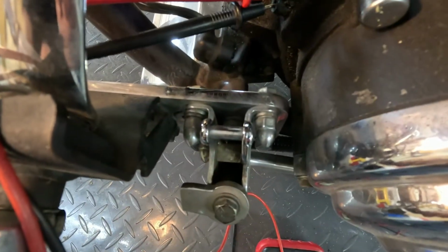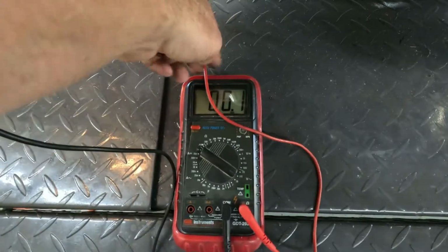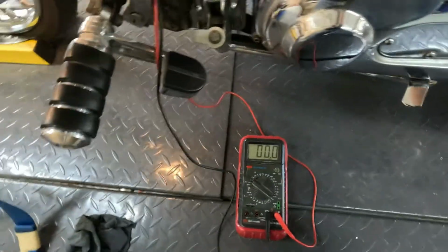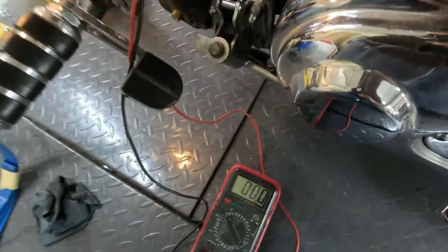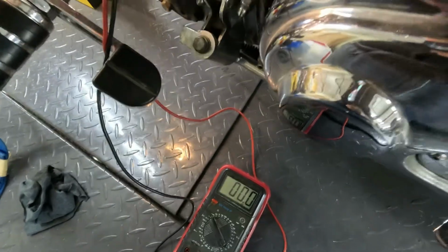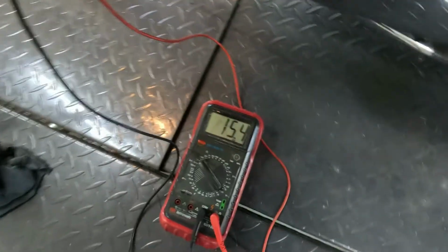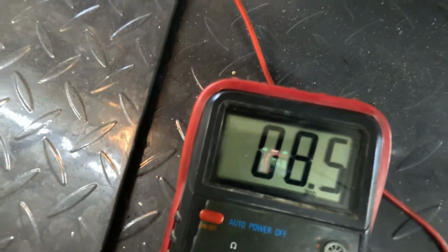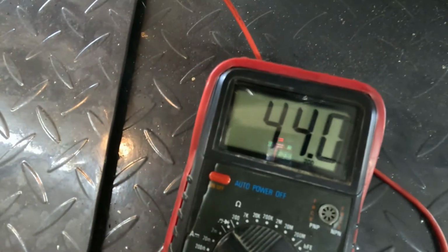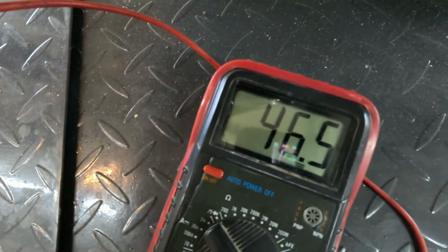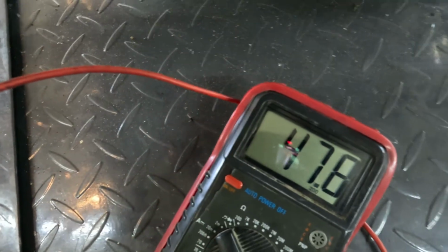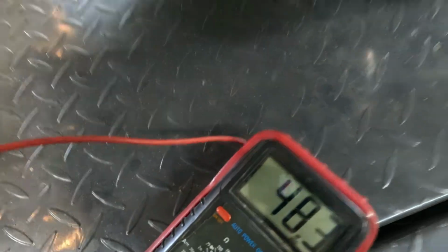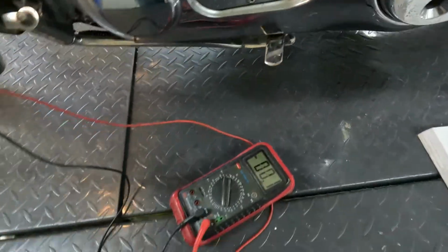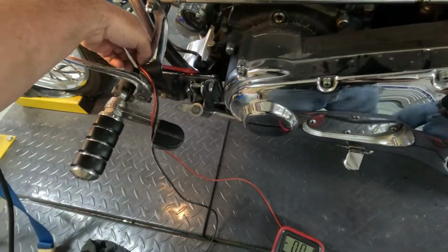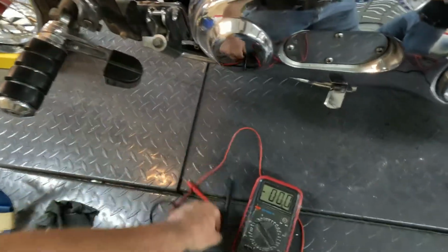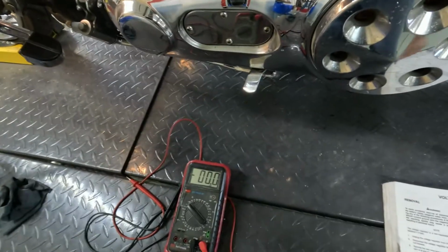One probe in each terminal. We're going to fire it up and see what kind of reading we get here. All right, looks like it was putting out 45 to 50 volts. So our stator is putting out a little stronger voltage than what the book recommends.